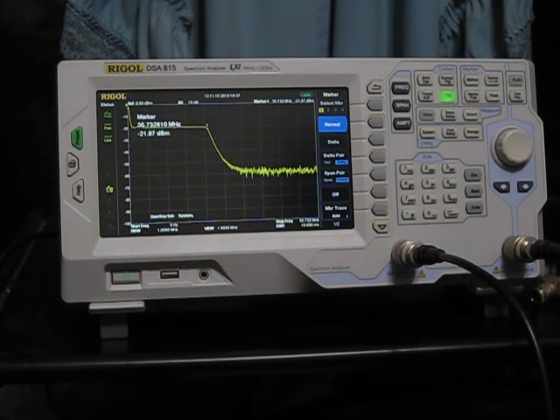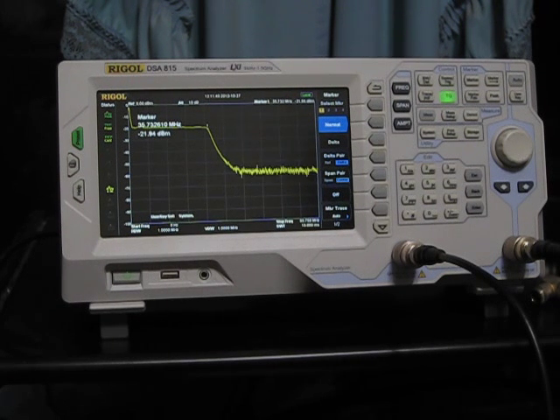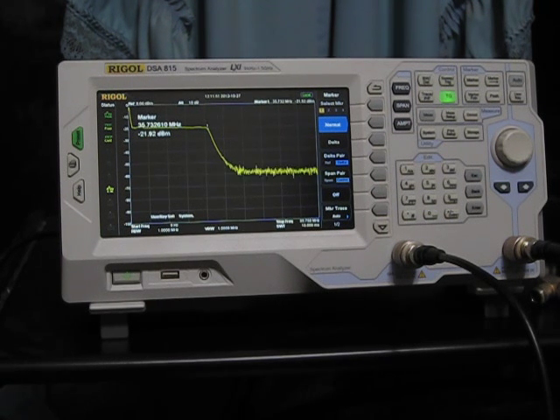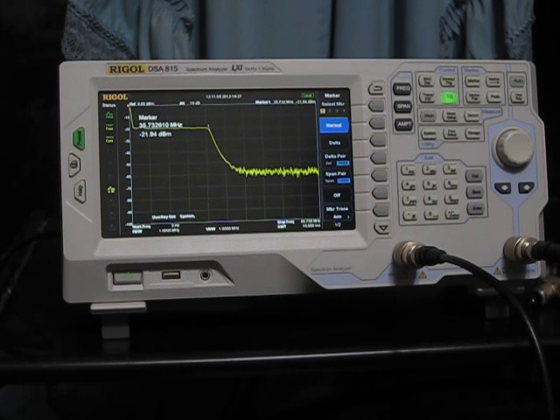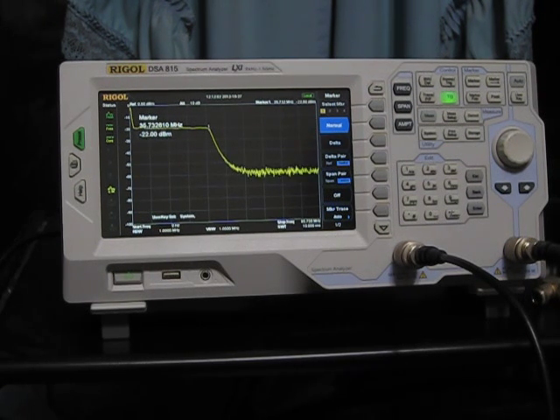I can't say enough times how much it's a good bang for the buck because I've compared the 1000 series specs with this one, and they're like marginally better than this. And actually this has a couple of options I believe that the 1000 series does not because this one just was released in like March or April of this year in 2012. And then there's I think an option that the 1000 series has that this doesn't. Now the 1000 series, like the 1030, goes up to 3 gigahertz and this one doesn't. But other than that, and the specs being just a little bit better on the 1000 series, this is pretty much in my mind, after looking through all that, just as good and as much of an analyzer spec-wise as the 1000 series is, just that it doesn't do quite as much and it doesn't go to 3 gigahertz.